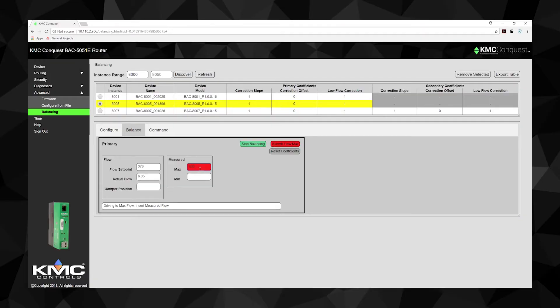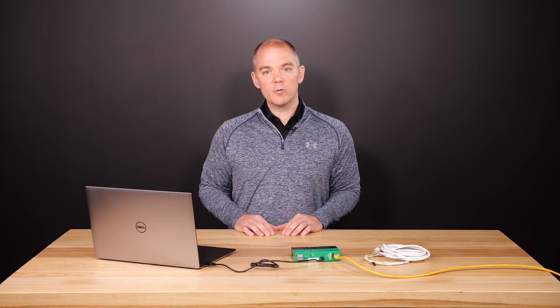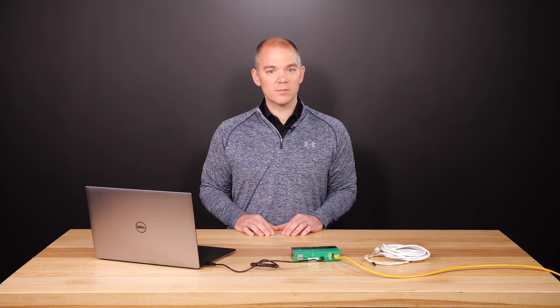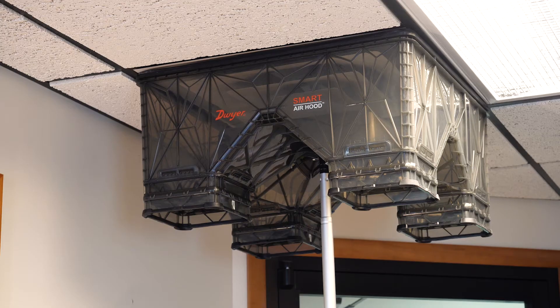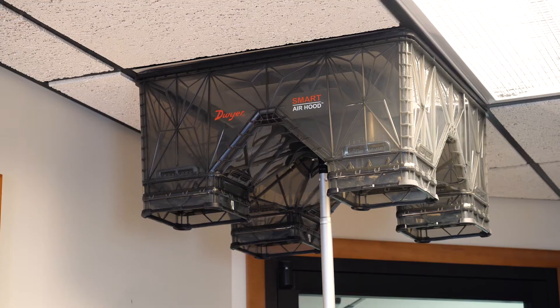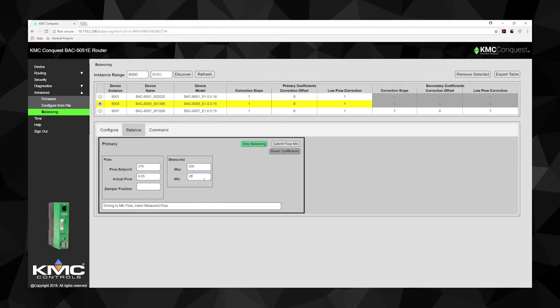The controller then repeats these steps to determine the actual minimum airflow. The VAV will position the damper for the lowest minimum airflow set point. Once the actual airflow value stabilizes, again measure and note the actual airflow with the flow hood. Enter the measured airflow in the measured min text box.